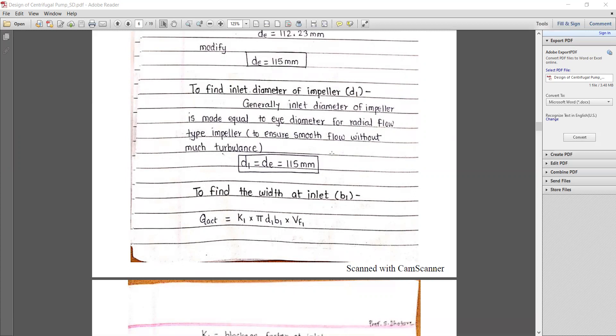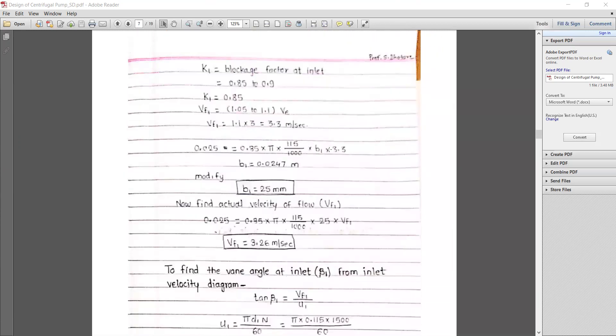For inlet width b1, using Q_actual = k1 × π × d1 × b1 × vf1, where k1 is the blockage factor at the inlet ranging from 0.85 to 0.90 — we use k1 = 0.85. The flow velocity at inlet vf1 = 1.1 × ve = 1.1 × 3 = 3.3 m/s.